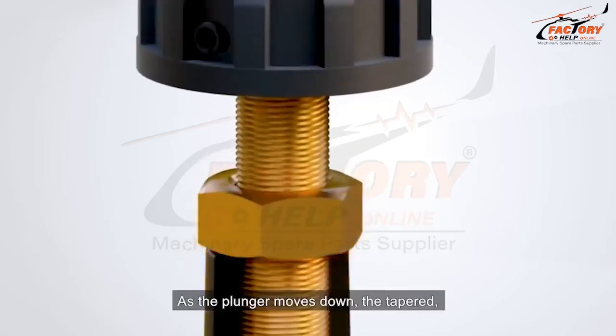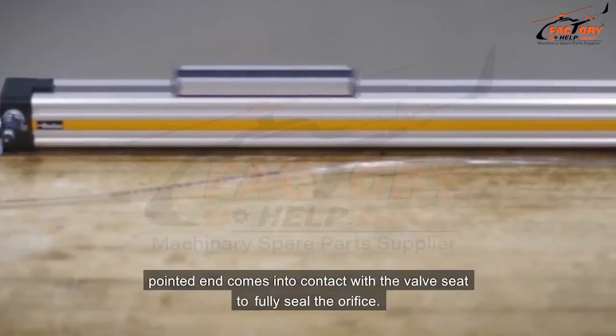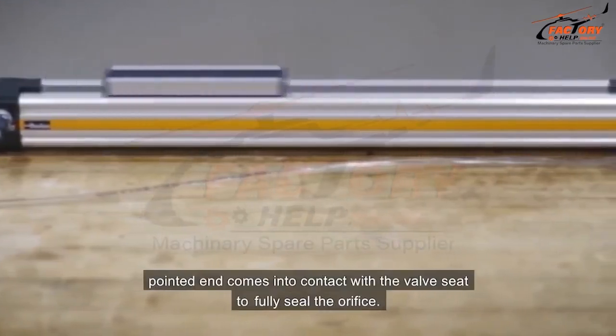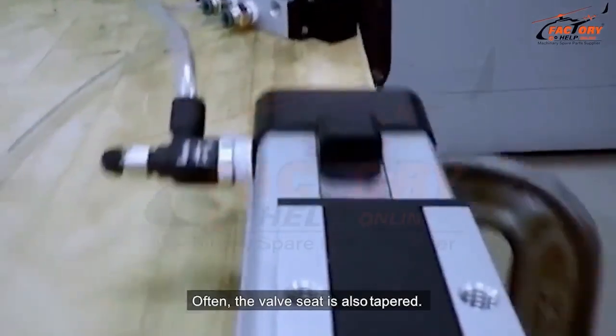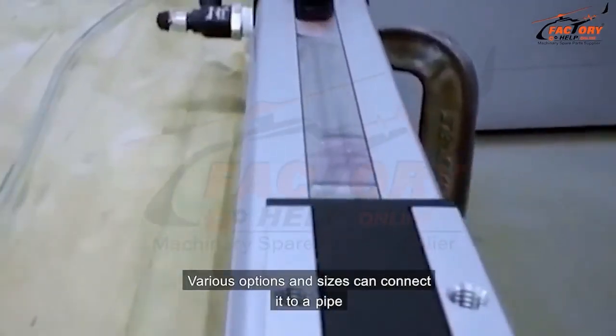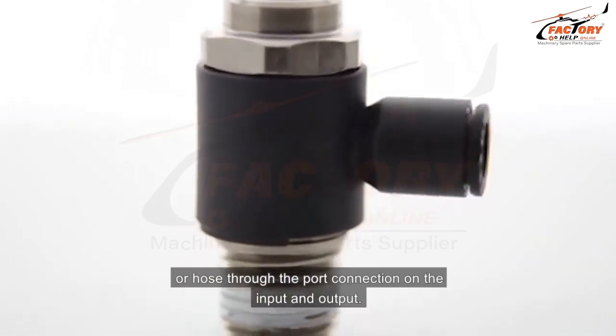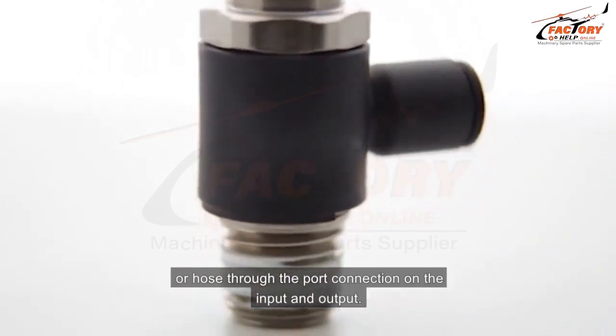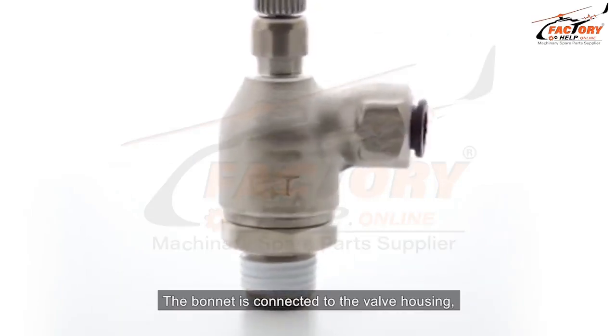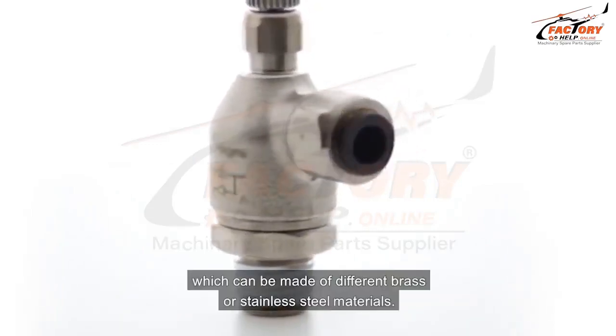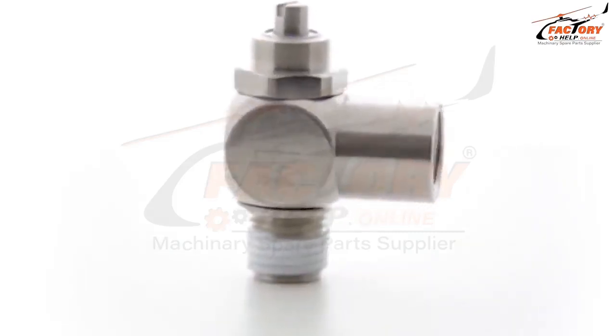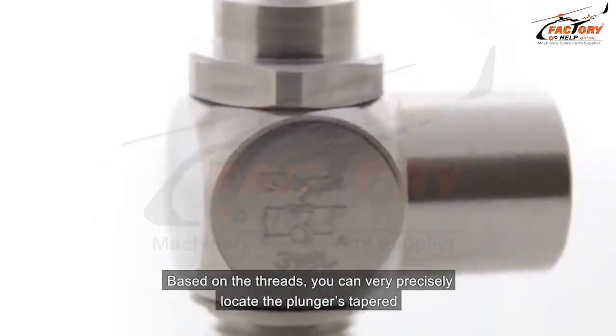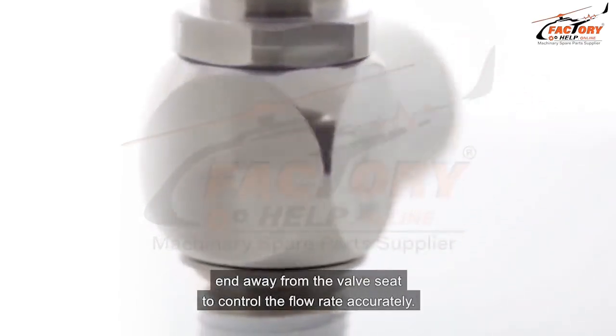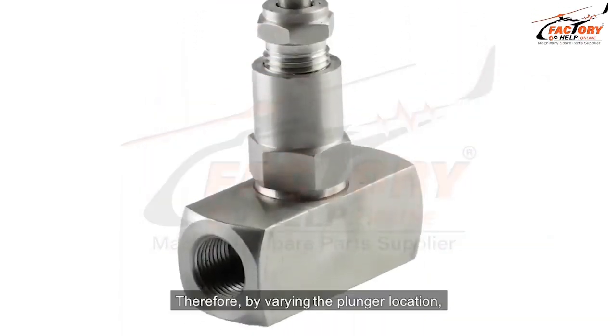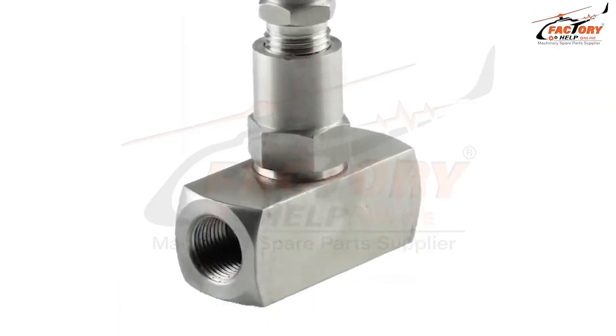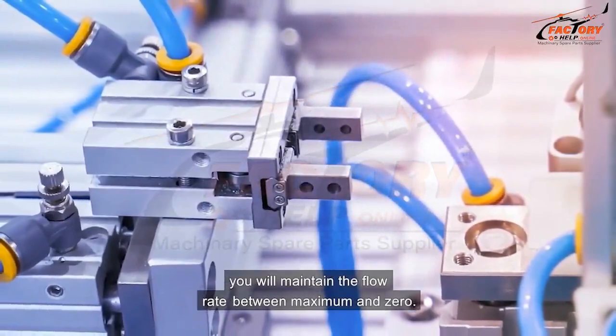As the plunger moves down, the tapered, pointed end comes into contact with the valve seat to fully seal the orifice. Often, the valve seat is also tapered. Various options and sizes can connect it to a pipe or hose through the port connection on the input and output. The bonnet is connected to the valve housing, which can be made of different brass or stainless steel materials. Based on the threads, you can very precisely locate the plunger's tapered end away from the valve seat to control the flow rate accurately. Therefore, by varying the plunger location, you will maintain the flow rate between maximum and zero.